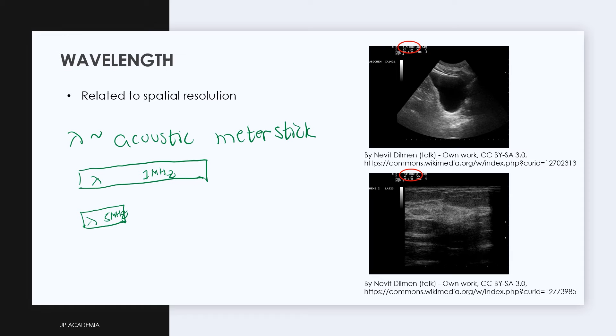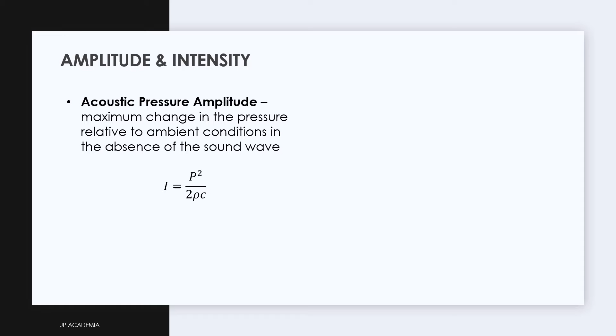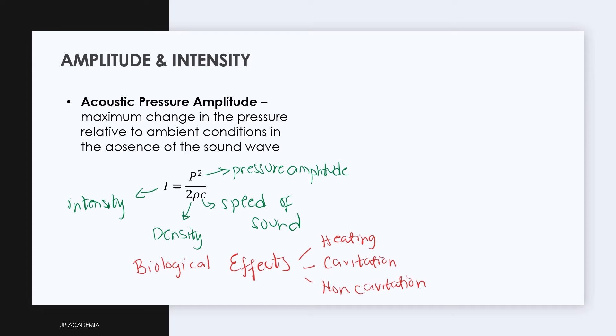Acoustic pressure amplitude is important to quantitatively describe the strength of a sound wave. It is defined here as the maximum change in the pressure relative to the ambient conditions in the absence of sound wave. This is related to loudness when we are talking about audible sounds. To quantify the intensity at a certain location, we have this expression: I is equal to P squared over 2 rho C, wherein P is the pressure, rho is the mass density, and C is the speed of sound. In addition, this quantity is useful when talking about possible biological effects of ultrasound, such as the production of heat during ultrasound attenuation, generation of tiny bubbles called cavitation, and non-cavitation effects such as displacement of particles in the medium.